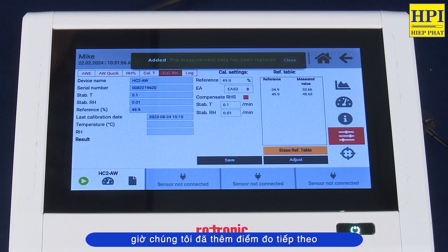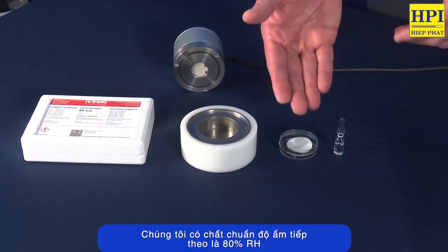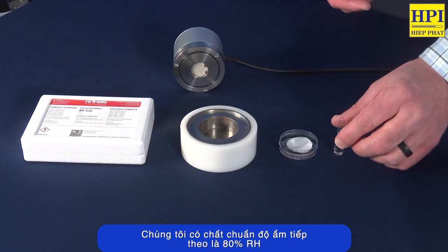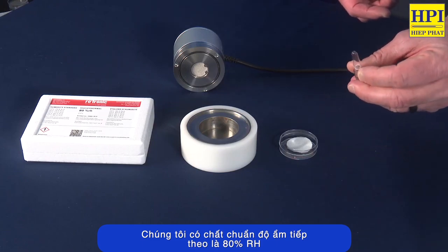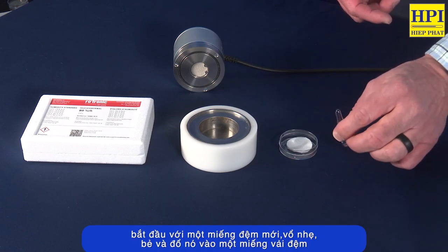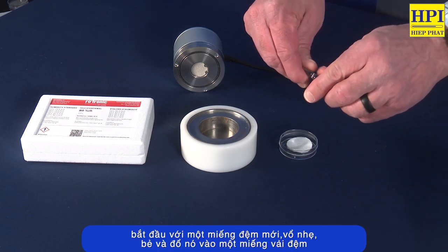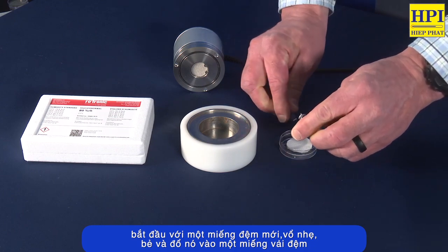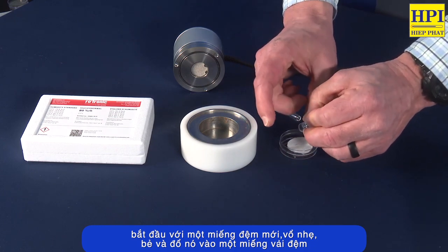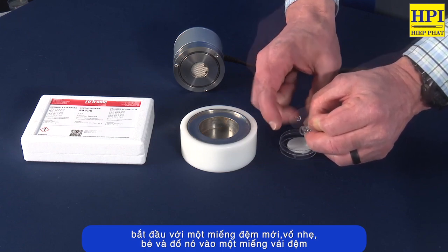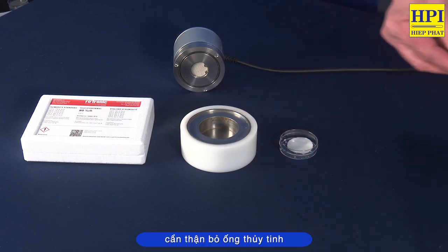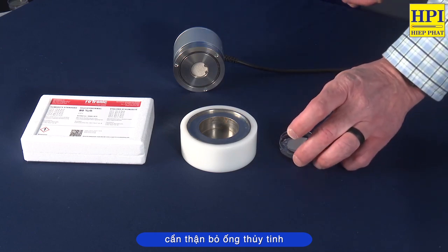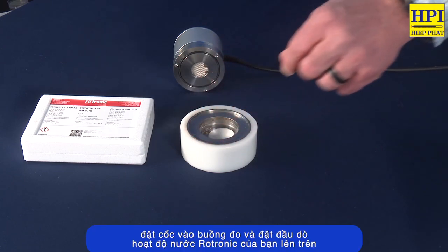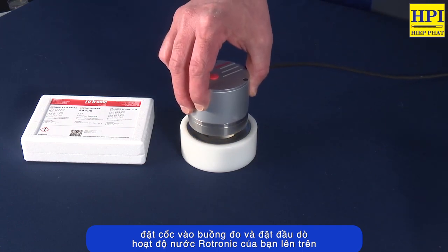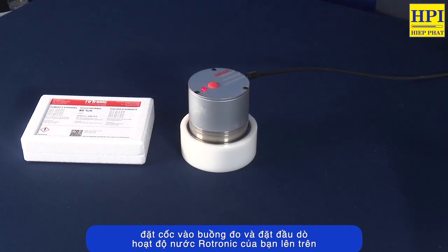We've now added the next measurement point, and we can go and complete our sample preparation as we've done previously. We want to start with a fresh fiber disc pad. We have our next humidity standard, 80% RH. We've tapped the vial so the contents are at the bottom. Once again, at the perforation, carefully break the glass ampule and empty the contents onto the fiber disc pad. Once the full content has been emptied, again, carefully discard the glass vial, place the sample cup into the sample cup holder, and place the Rotronic water activity probe onto the sample cup holder.